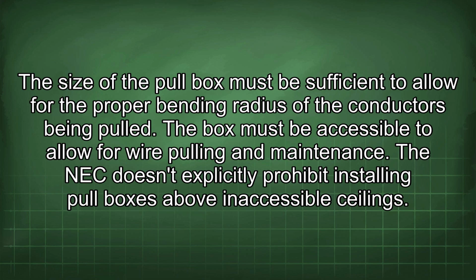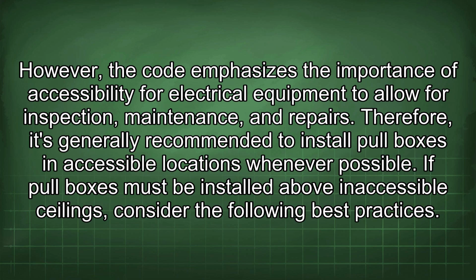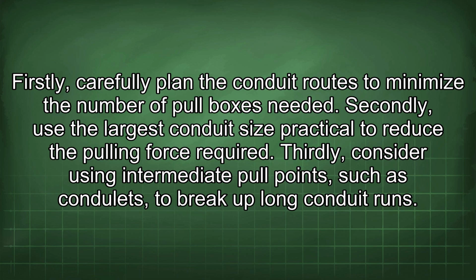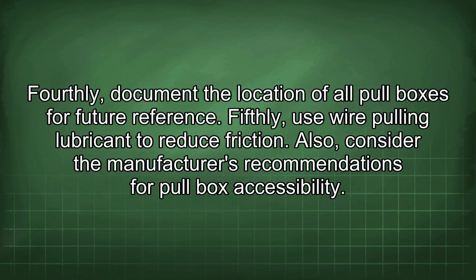The NEC doesn't explicitly prohibit installing pull boxes above inaccessible ceilings. However, the code emphasizes the importance of accessibility for electrical equipment to allow for inspection, maintenance, and repairs. Therefore, it's generally recommended to install pull boxes in accessible locations whenever possible. If pull boxes must be installed above inaccessible ceilings, consider the following best practices. Firstly, carefully plan the conduit routes to minimize the number of pull boxes needed. Secondly, use the largest conduit size practical to reduce the pulling force required. Thirdly, consider using intermediate pull points, such as condulets to break up long conduit runs. Fourthly, document the location of all pull boxes for future reference. Fifthly, use wire pulling lubricant to reduce friction.